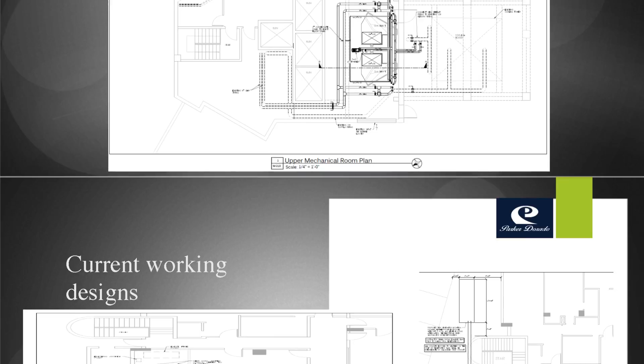The new design is bringing your building back up to what it was originally intended to provide. You have the steam boiler that provides reheat or dehumidification, but to save energy, the new design and concept is utilizing the cooling tower.